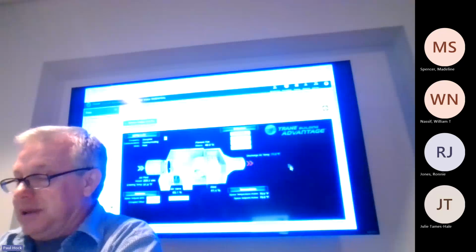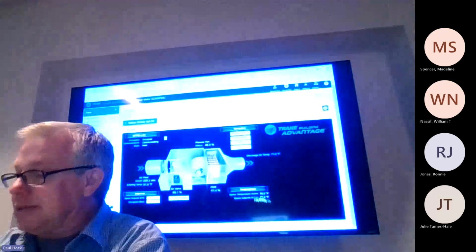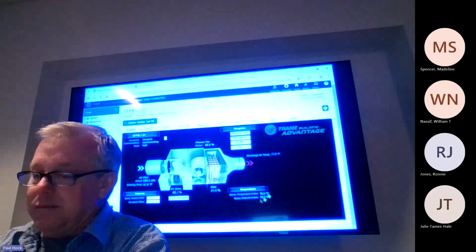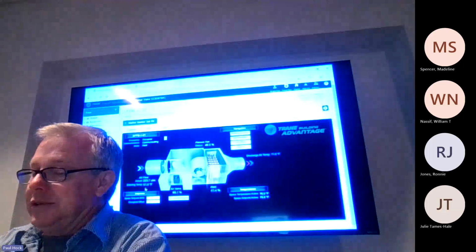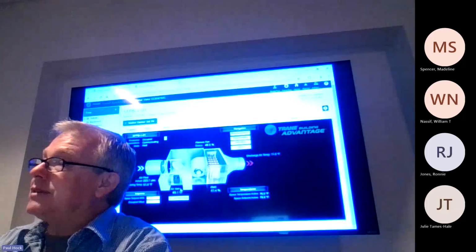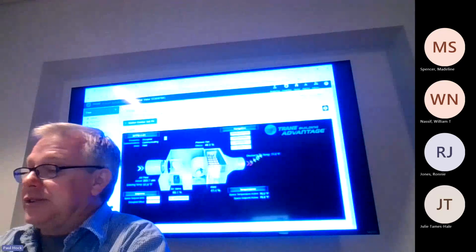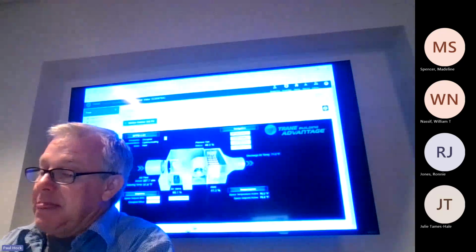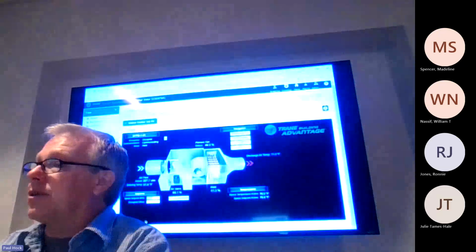Right now, this is telling you what the space temperature is and what your set point is. So we're half a degree off, pretty good. It tells you your airflow, your entering temp coming from the air handler, where the air valve is on that unit for this room, your heating, your discharge air temp, and your fan status tells you what your fan speed is. Now you can change the set point here also, if somebody's hot or cold.